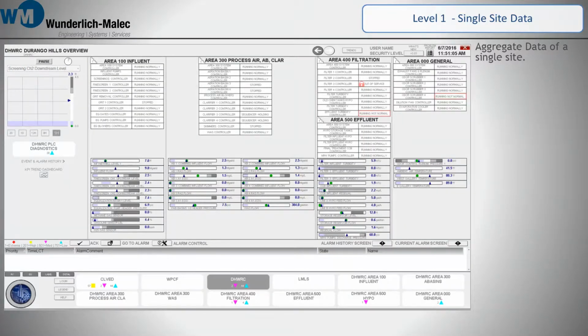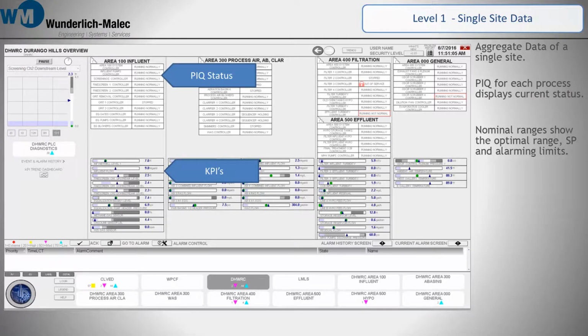Situational awareness comes in, and the screen now focuses less on the layout and individual equipment of the plant and instead on the data and operation. The PIQ, which is the process intelligence of each system, gives the current status of every area. Nominal range KPIs show the set point, optimal range, and alarming limits of each process variable.